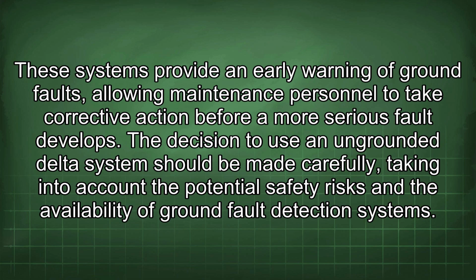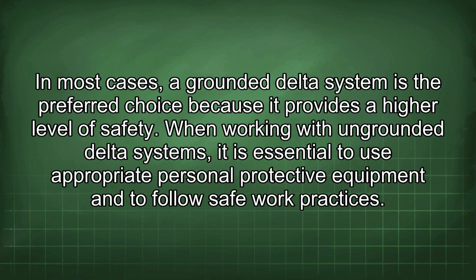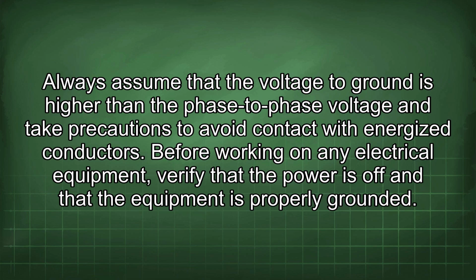These systems provide an early warning of ground faults, allowing maintenance personnel to take corrective action before a more serious fault develops. The decision to use an ungrounded delta system should be made carefully, taking into account the potential safety risks and the availability of ground fault detection systems. In most cases, a grounded delta system is the preferred choice because it provides a higher level of safety. When working with ungrounded delta systems, it is essential to use appropriate personal protective equipment and to follow safe work practices.